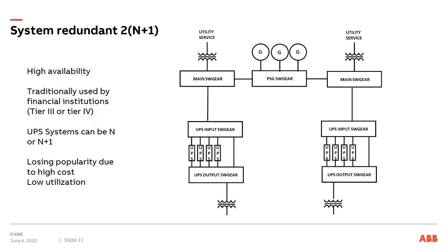The configuration I'm showing here is what was very commonly used in large data centers pretty much until the colo and cloud era. There are some financial institutions that still would use something like this, but even they are not doing this. It's referred to as system redundant, or 2N+1. The Uptime Institute is an organization that came up with a way of grading data centers, a tier level certification where tier 1, 2, 3, 4, it's not used anymore, but a tier 4 data center would be known as fault tolerant and concurrently maintainable.